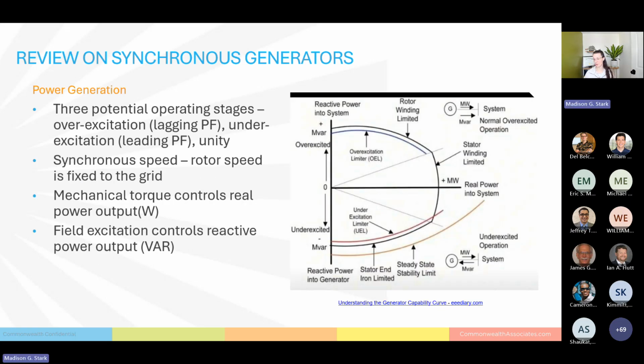So the power generation component, and this is really where you get into the meat and potatoes of what is electrical as opposed to mechanical. A synchronous generator can operate in three different stages: overexcitation, underexcitation, and then unity, which is really kind of an ideal scenario that doesn't happen much. So in overexcitation, the generator is creating both watts and VARs. So it's creating real power and reactive power, and it's pushing that all into the grid. So in overexcitation, we're pushing both watts and VARs into the grid.